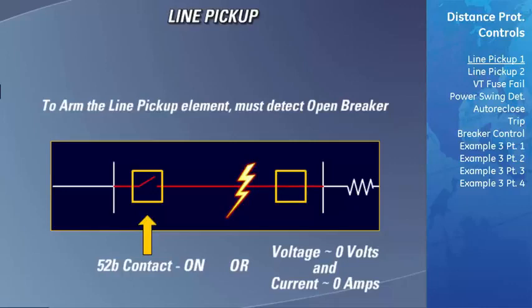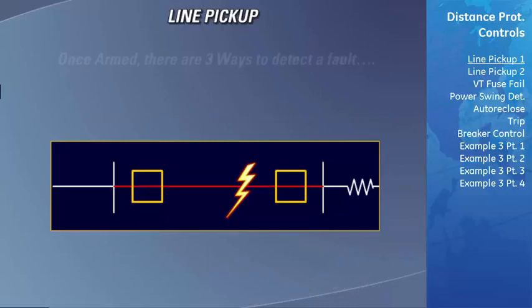Once the line pickup element has been armed by detecting that the breaker leading into the transmission line has been opened, there are three different ways that the line pickup element will detect that the breaker has been closed onto a fault and then signal the D60 to trip the breaker.